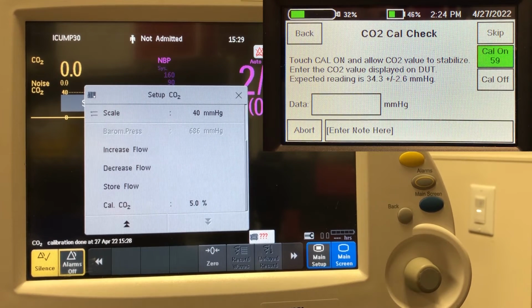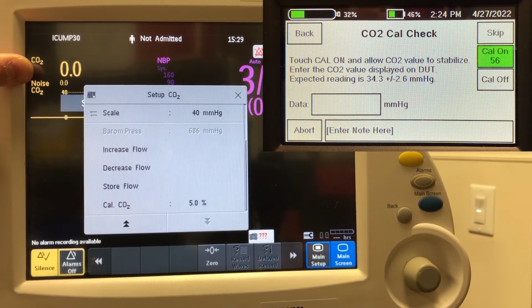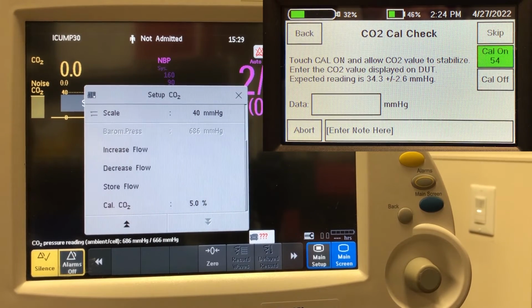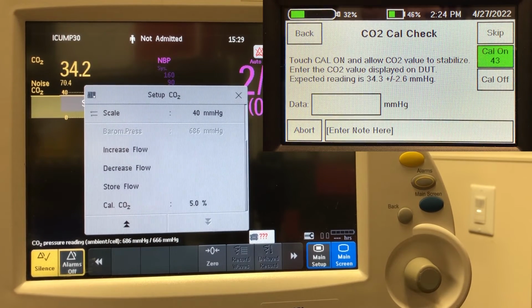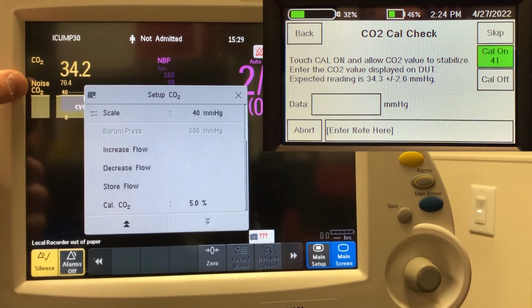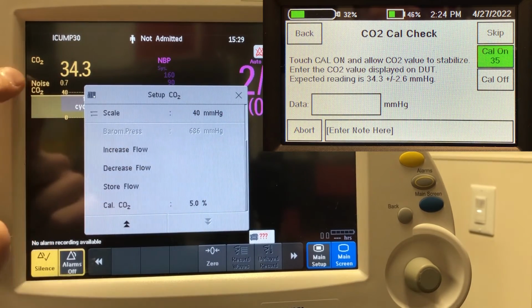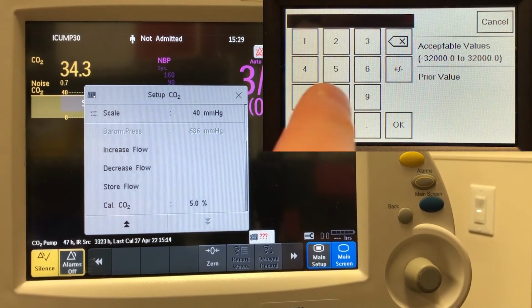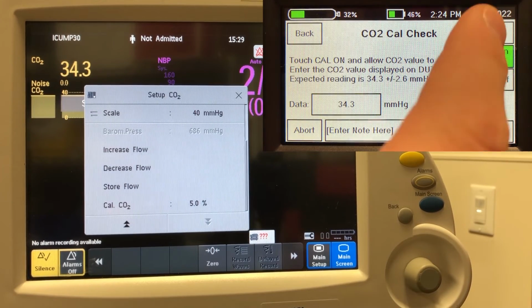So now we're going to do a cal check, so we turn the cal gas back on. We watch this value up here, the actual end tidal CO2 value. In this service mode, it calculates it continuously. And that should be 34.3 plus or minus 2.6. We want to wait till the noise is settled down. That tells us that the reading is stable. Okay, so 34.3, so it's actually exactly on what it's supposed to read. Okay, so that's done. We hit next.